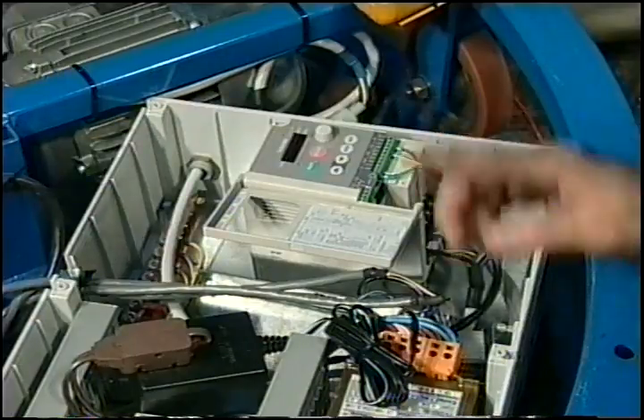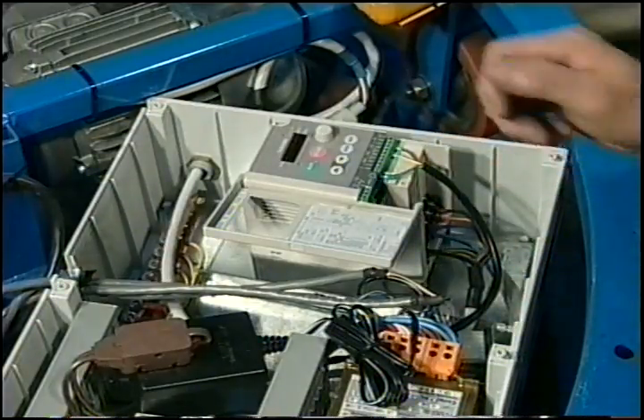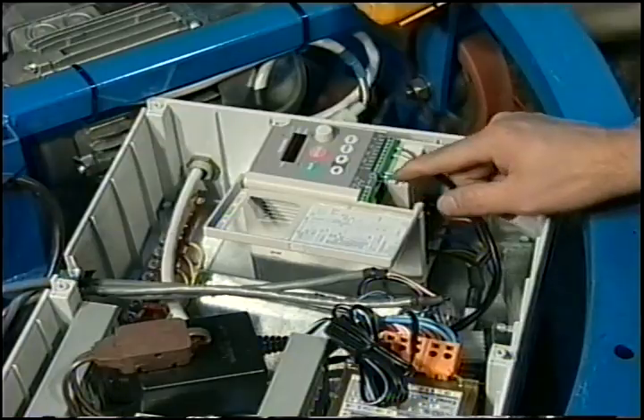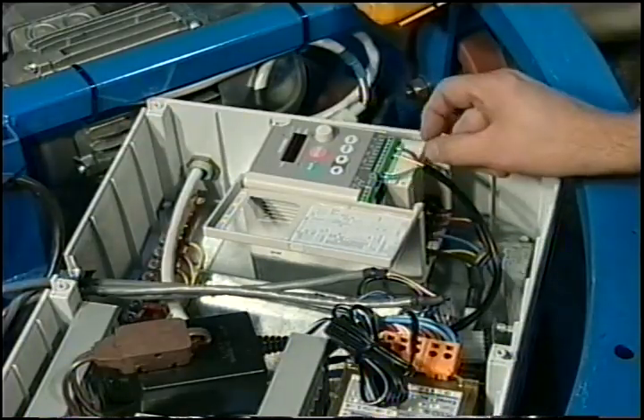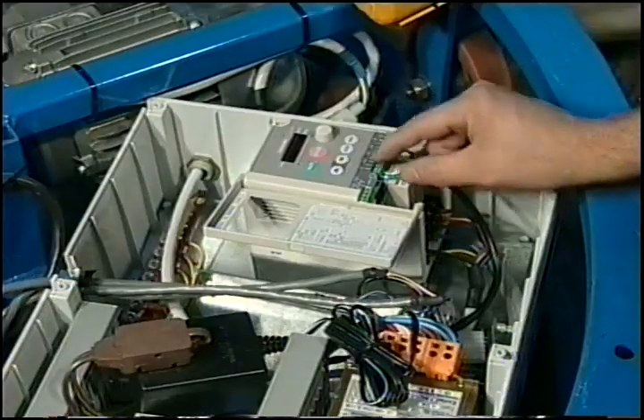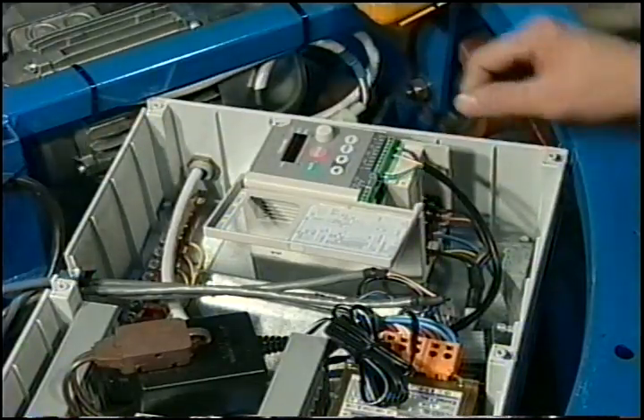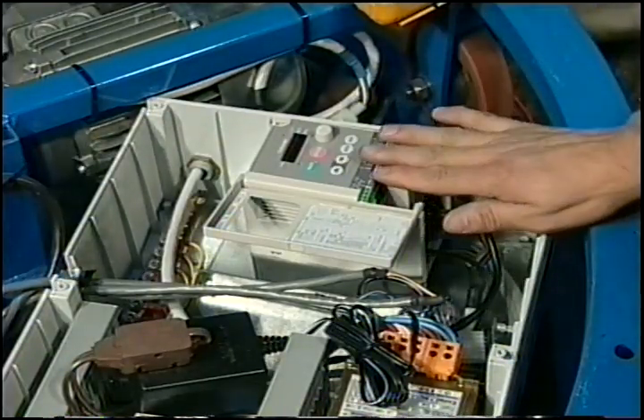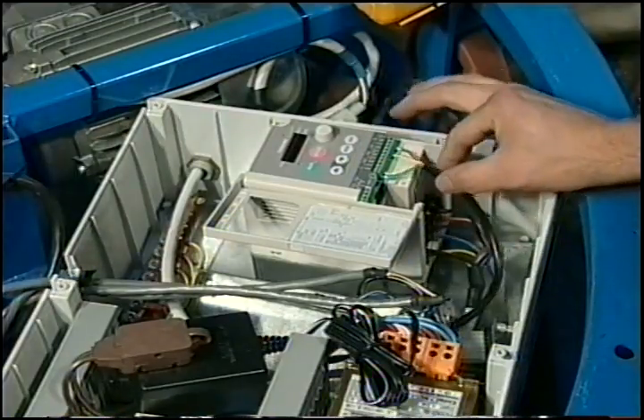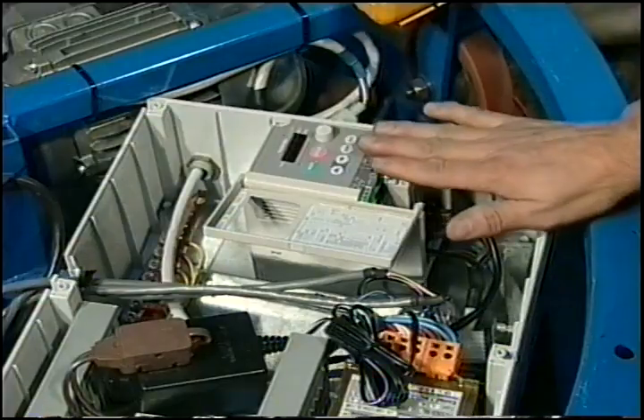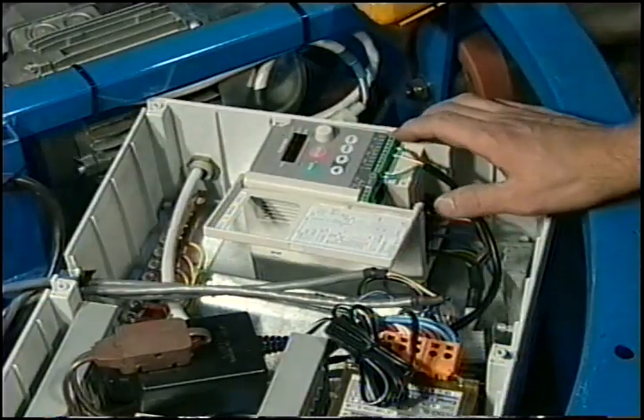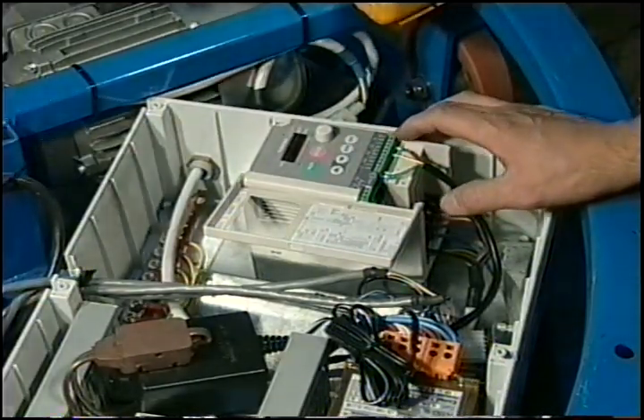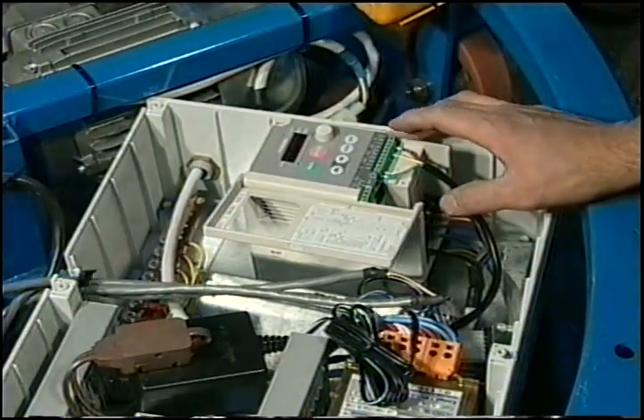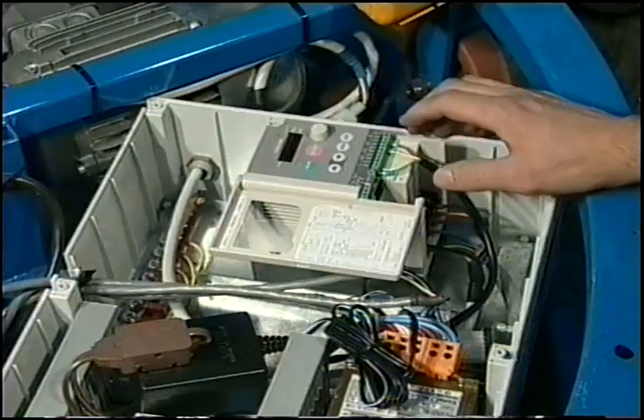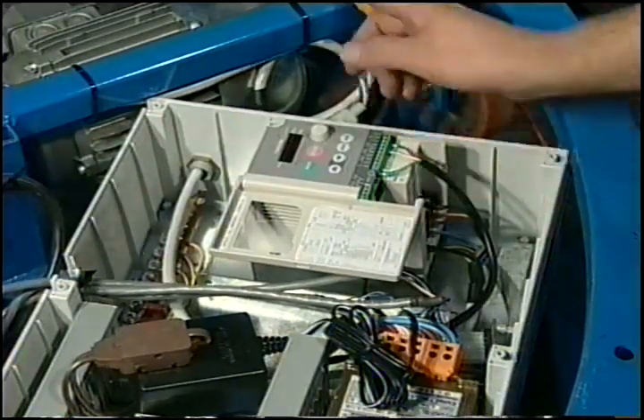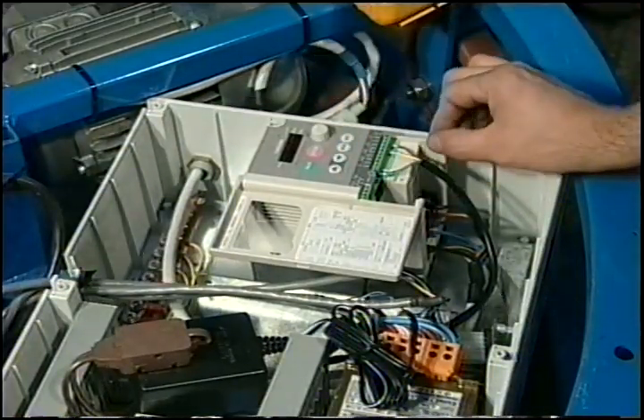Once the CPU, after you coin up, wants it to go left or right, it takes away one of the voltages to either the left or the right, and that's what makes it start to rotate. Okay? So these terminals up here are for your command control from your CPU board that's telling the inverter what to do.